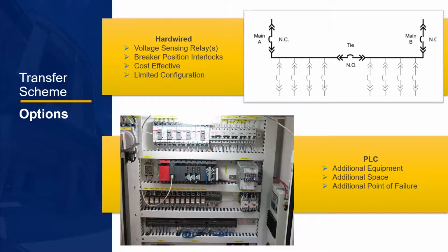Traditional interlocking schemes utilize non-sophisticated under and over voltage relays and breaker position contacts to support operation, but they severely limit the flexibility of the main operation. In other cases, programmable logic controllers, or PLCs, provide a means of operating the scheme, but by utilizing the relays themselves, we cut down on costs, real estate, and eliminate another potential point of failure.